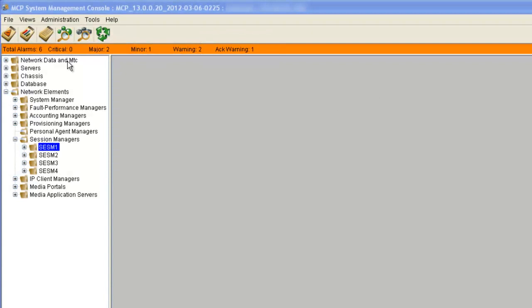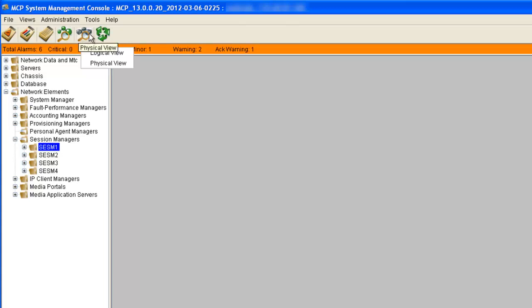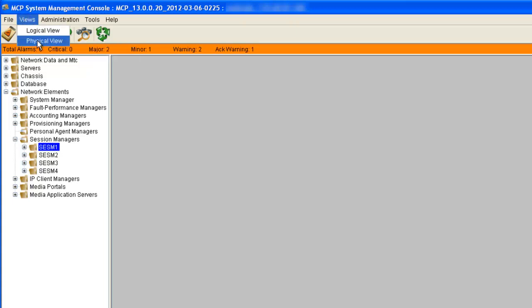If you have a lot of alarms, it can be difficult to find the element that is having problems — you have no indication of which device is in alarm on the side. There is a way we can view our devices in a logical format and see the alarm. There are a couple of ways we can open it up: we can right-click on the alarm banner and select logical view or physical view. We also have these buttons here — the logical view button and the physical view button. And under the view menu, we can also click on the logical view or the physical view.